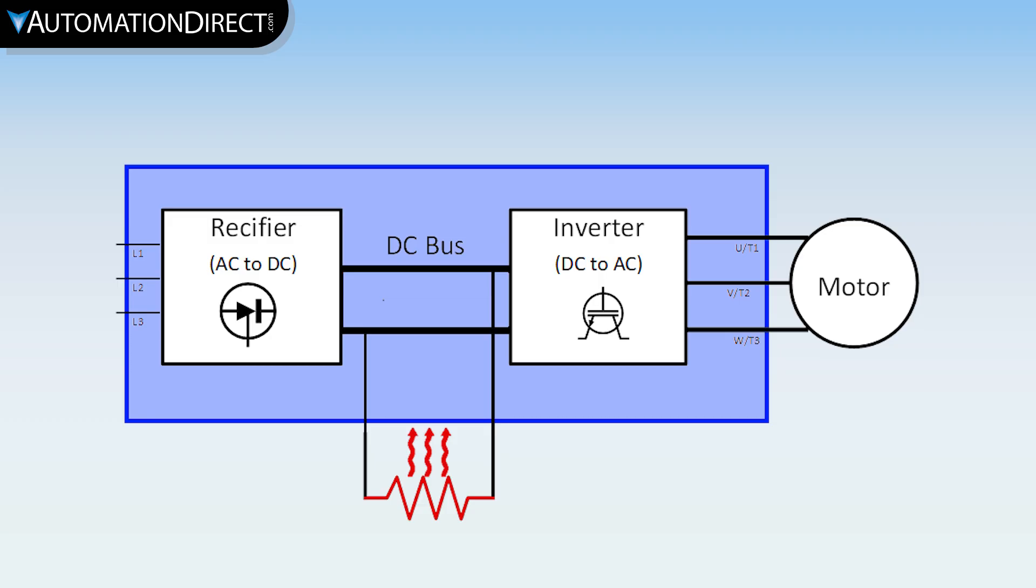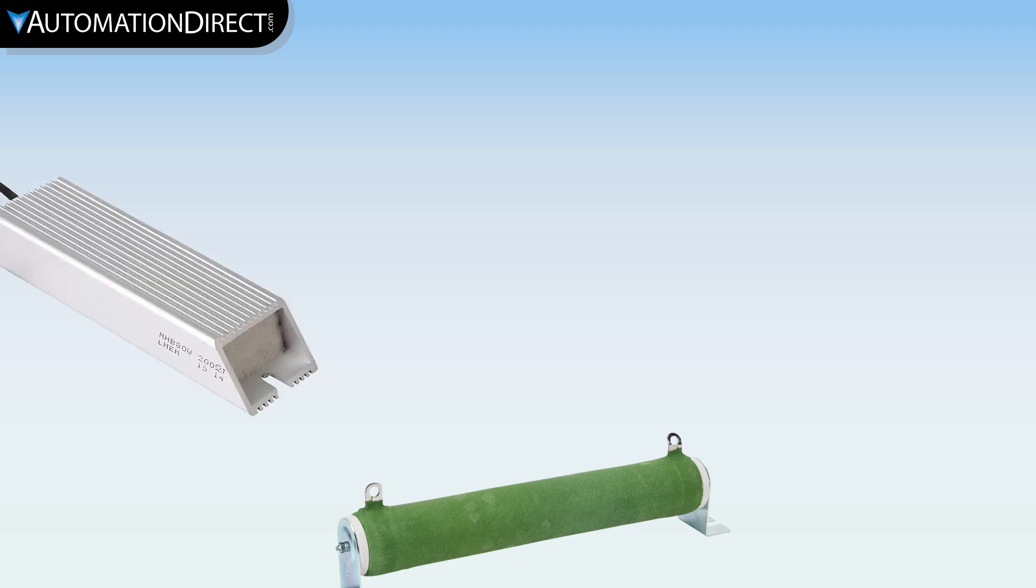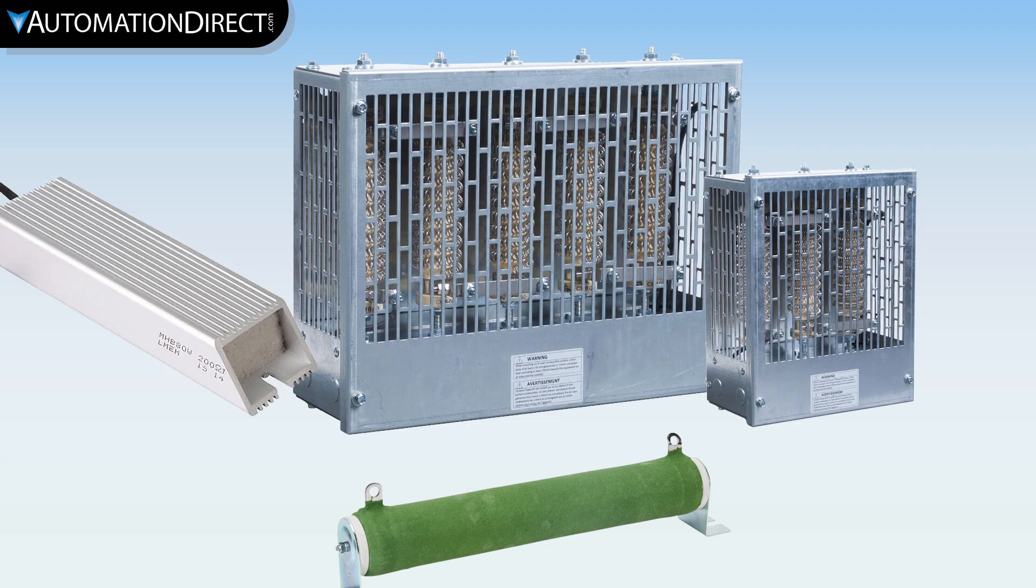Usually, the best practice is for the braking resistor to be mounted outside of the drive enclosure. Most braking resistors are sold either open-style, encapsulated, or in ventilated NEMA-1 enclosures. Whatever style is used, ensure there is sufficient airflow and ventilation to deal with the heat.